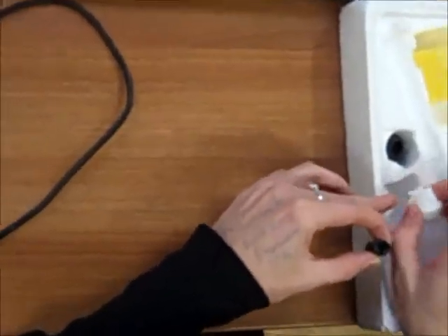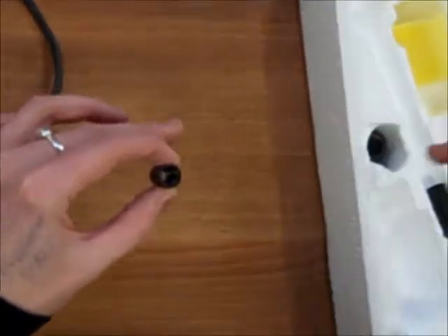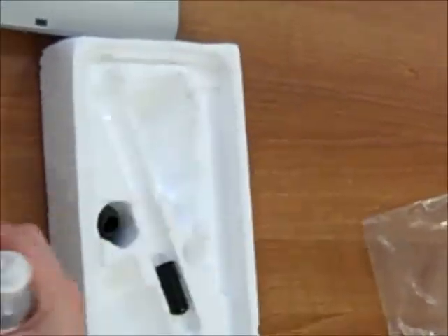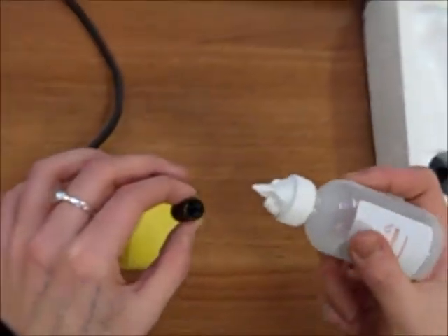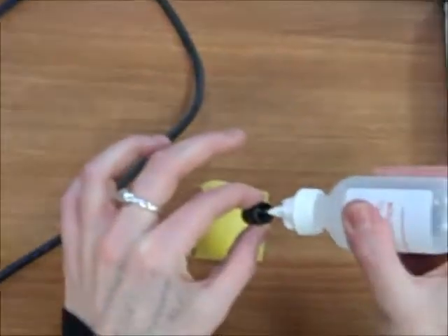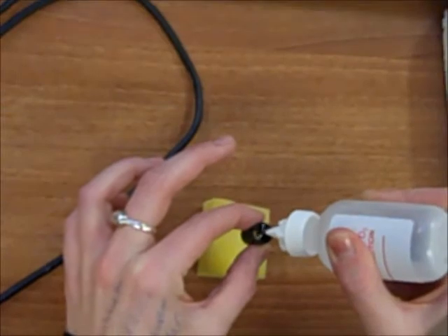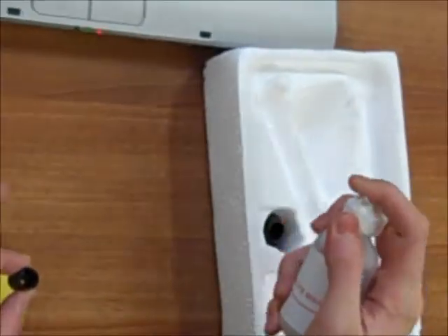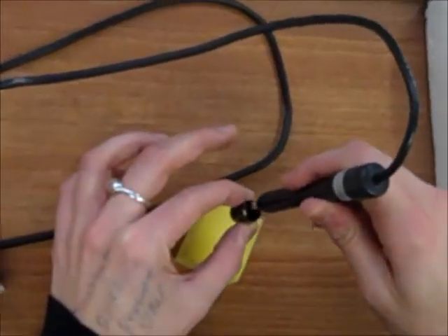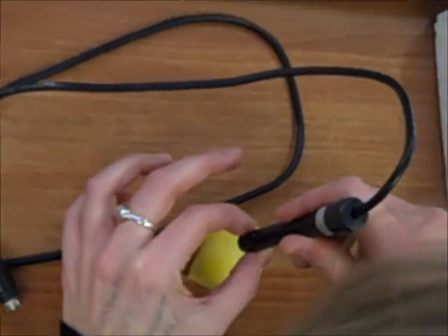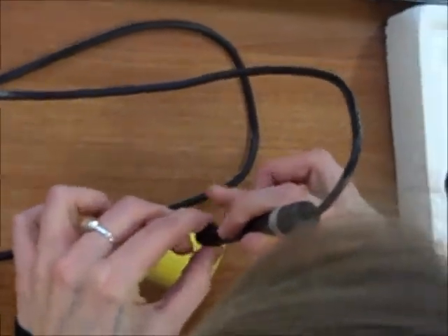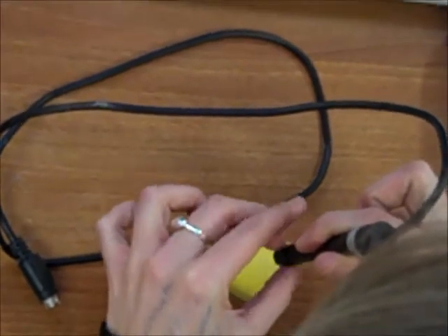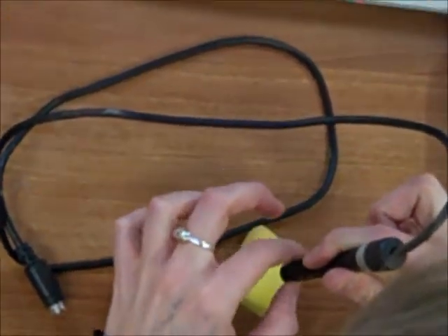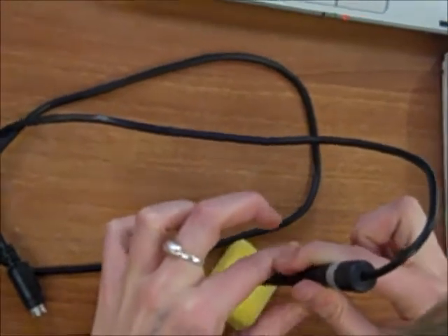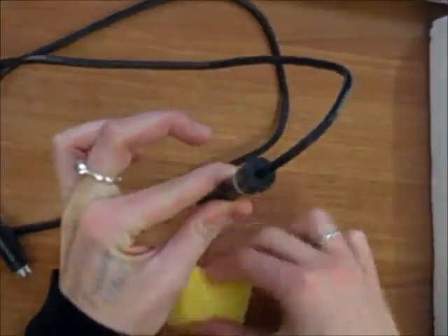What we need to do to that is fill it with some simple electrolyte solution. The reason we do that is so that there's no air bubbles or air at all between the probe and the membrane. So just fill it up right to the rim, so it's almost overflowing. Like that. And then simply put it in and screw it in. There will be some leakage, but that's fine. It's just to ensure that there's no air in there at all. So screw that on, like so. And then just use the sponge to wipe it off.